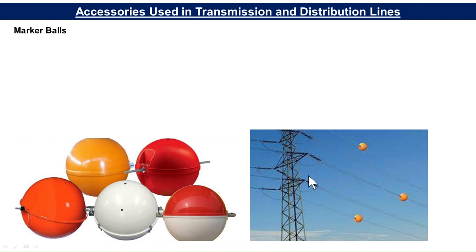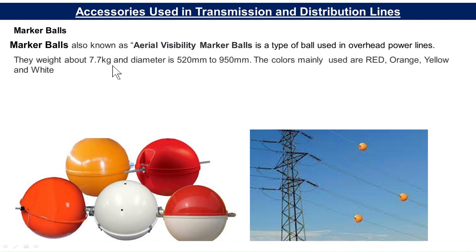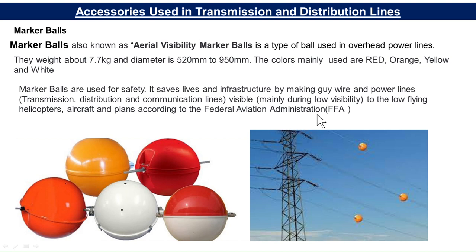Then there are marker balls, which you have seen suspended on various transmission lines. Marker balls, also known as aerial visibility marker balls, are used on overhead power lines. They weigh about 7.7 kg, with diameters ranging from 520 mm to 950 mm. The colors mainly used are red, orange, yellow, and white. They are used for safety — making guy wires and power lines visible to low-flying helicopters, aircraft, and planes, according to the Federal Aviation Administration. They are generally used on transmission lines near airfields.